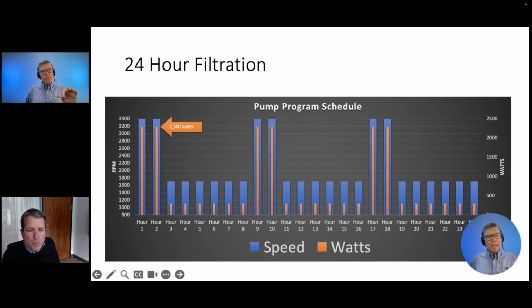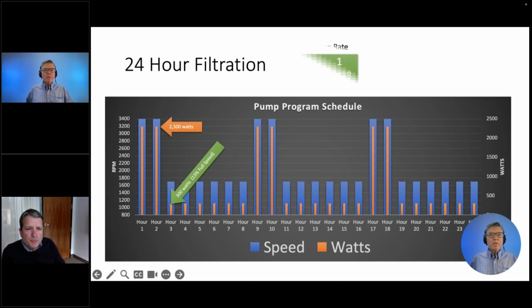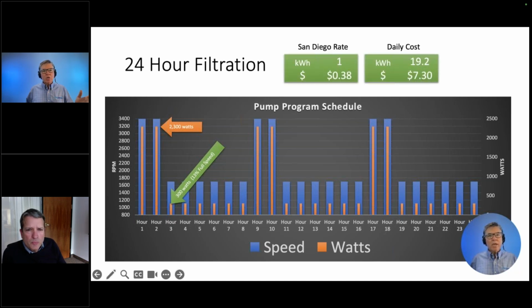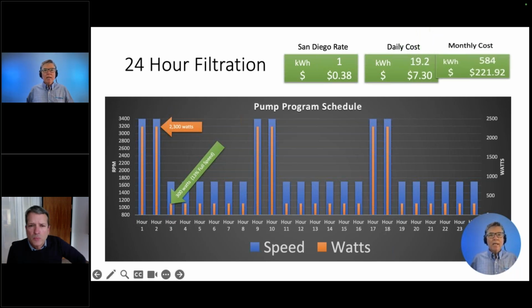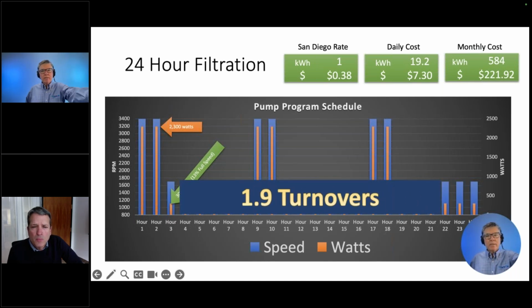Now, what I want you to look at is we got our high and our low watts. So on low speed, we're down at 300 watts. High speed obviously stayed the same. So if we look at this, our San Diego rate hasn't changed. Our kilowatt hours are approximately the same. We're looking at $7 a day. And in this case, because this is running on high speed and it doesn't need to, but I use the worst case scenario to make this illustration. So for the same amount of money, approximately, of running that variable speed for 8 hours and turning it off for 16, you can run it 24/7 or run it 22 hours, kind of a thing.